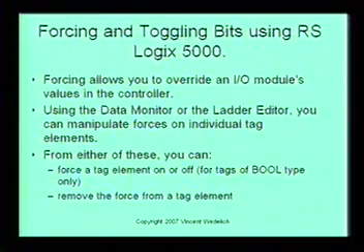Next, we're going to move to forcing and toggling bits using RS Logix 5000. Forcing allows you to override an I/O module's values in the controller. Using the data monitor or the ladder editor, you can manipulate forces on individual tag elements. From either of these, you can force a tag element on or off for tags of BOOL type only, and remove the force from a tag element.